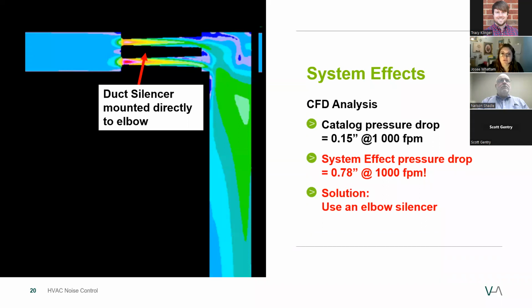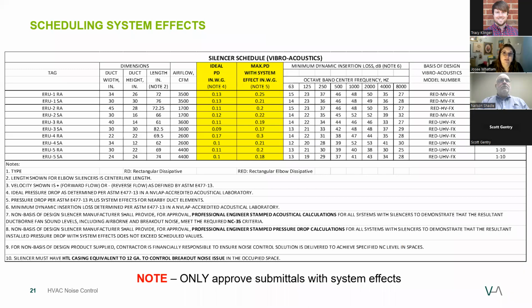It measured 0.78 inches at the same airspeed. So a solution here would be to use an elbow silencer to minimize system effects of pressure drop and self-generated noise. Another more proactive solution, though, would be to show system effects in a silencer schedule. Probably the best product out there to avoid pressure drop problems is a silencer schedule. You can use this to specify the pressure drop, including system effects. It would greatly reduce your risk because we are showing that we're applying the silencer and not just selecting it.